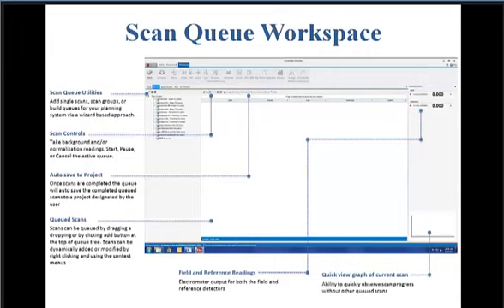The queue interface is similar for those of you who are familiar with, like, IBA's queue system. It's been a long time for me since I've used the PTW tank, but I believe they had a similar setup. You can set up queues. You see there on the left there's a tree of various different types of queues that we scan with detector names and what they're set up for. They have nice little, basically, VCR, even though that dates me, DVR, TV type controls for doing scan queue control. And you can auto set the scans to be dumped to a particular project if you're organizing your scans in project. It has a quick graphing of the current scan being scanned and then the dynamic field and reference readings for your detectors to see if your field and reference are appropriately placed in the field as you scan.